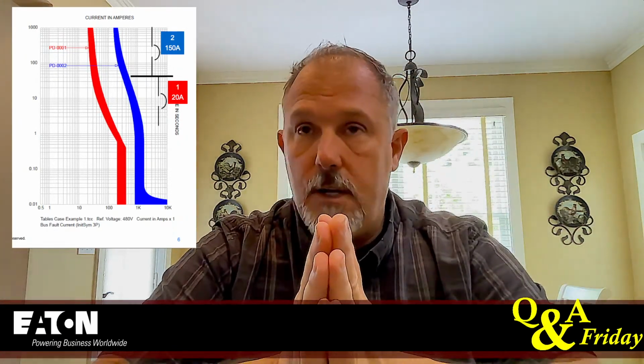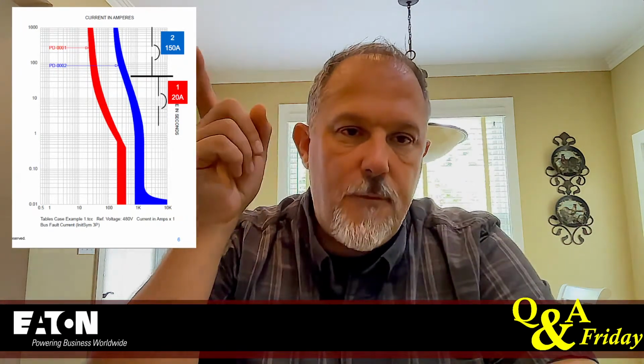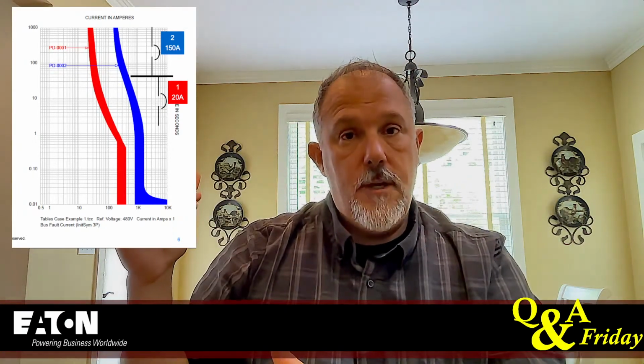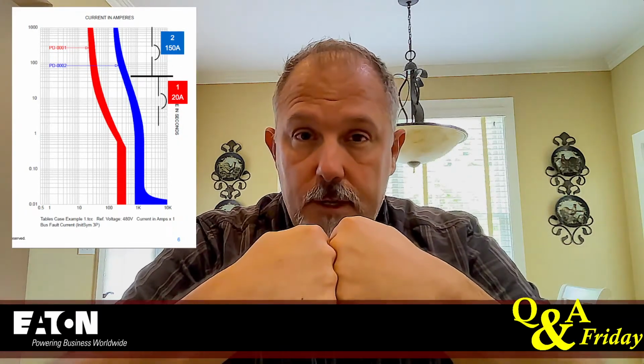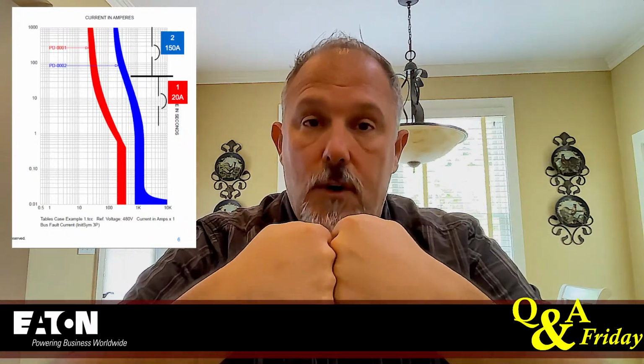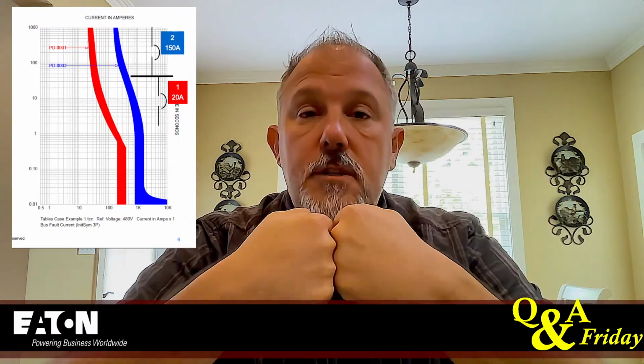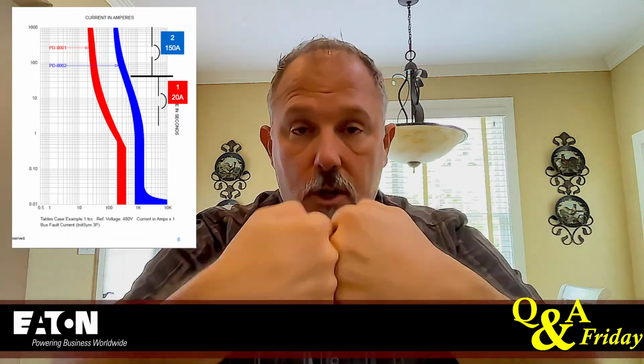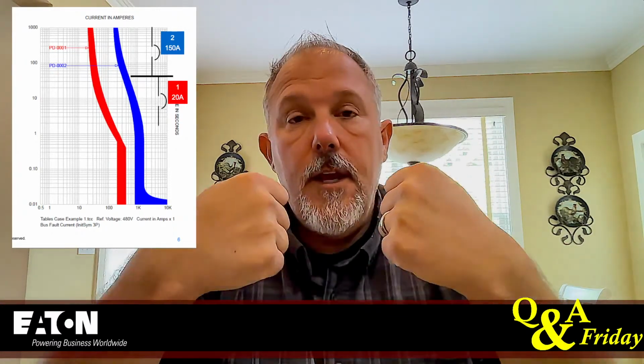So here are a couple ways to solve the problem. One, you can take that F150 and focus on the upstream device to make it go slower. That's basically what you want to do. You want that circuit breaker to hold its contacts closed long enough so that the downstream circuit breaker clears the fault and the upstream circuit breaker keeps its contacts closed. And you don't want chatter. You don't want those contacts to do this, because when you get this going on, it will create dimples. Dimples look good on you and me, but they don't look good on breaker contacts.